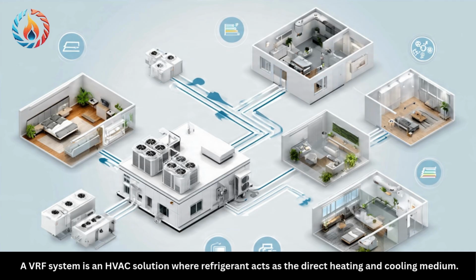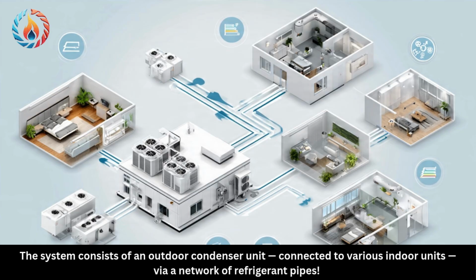What is a VRF system? A VRF system is an HVAC solution where refrigerant acts as the direct heating and cooling medium. The system consists of an outdoor condenser unit connected to various indoor units via a network of refrigerant pipes.